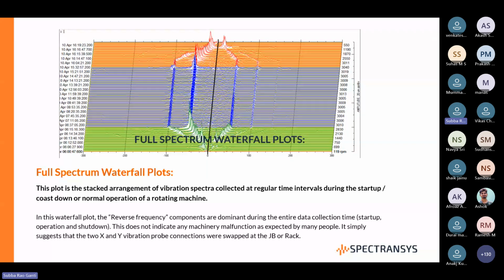So when you get an opportunity to stop the machine, because under normal running condition you can't disconnect the probes, it is not safe to do that, then when the machine shuts down, you go to the field and check whether X is connected to X or not. Definitely you will find that the probes have been swapped either at the junction box or at the rack itself. So even though this data is suggesting a full reverse spectrum, reverse precession, this is not physically possible.